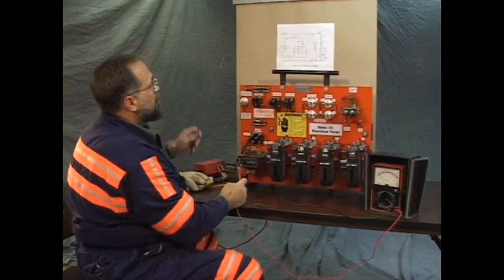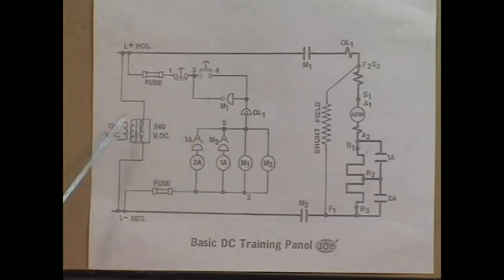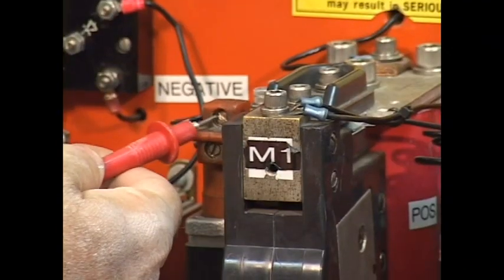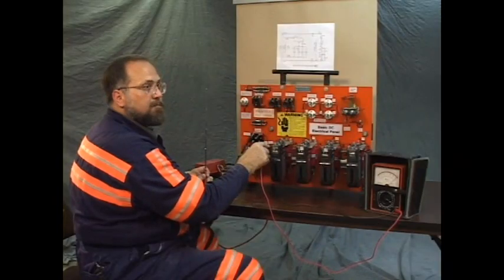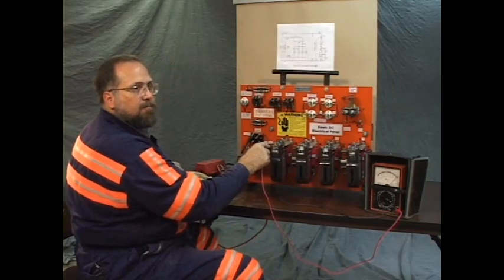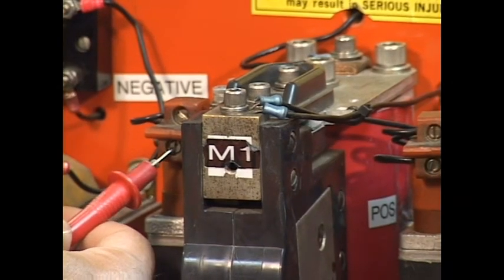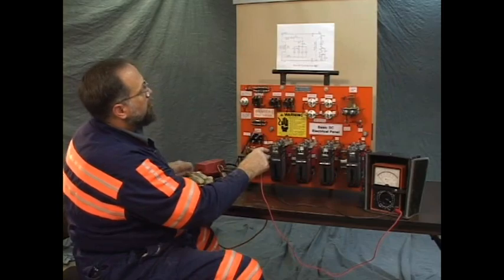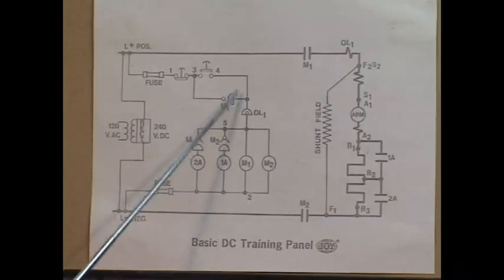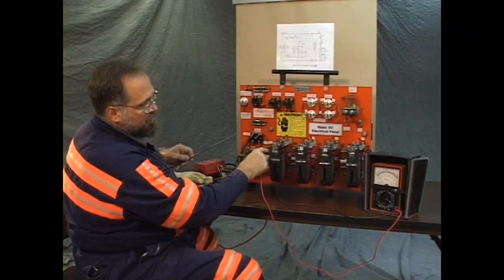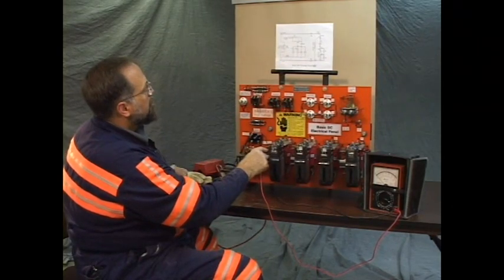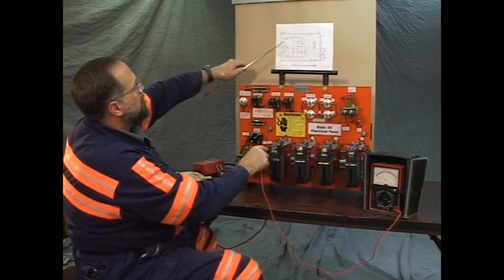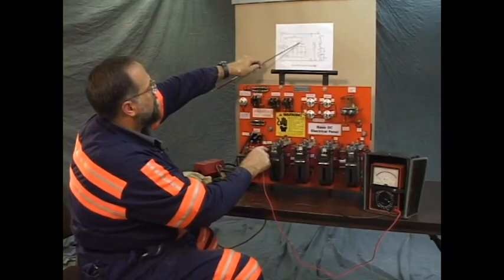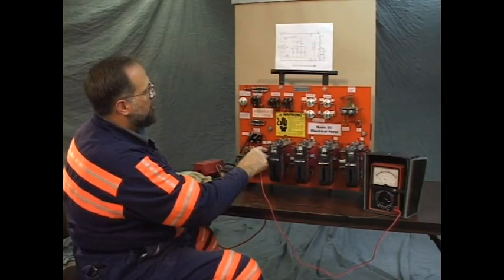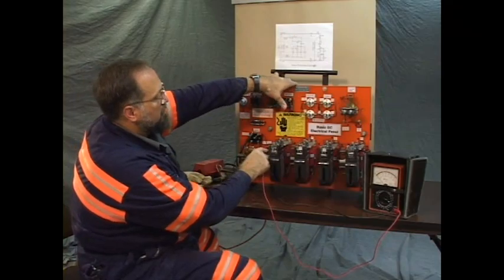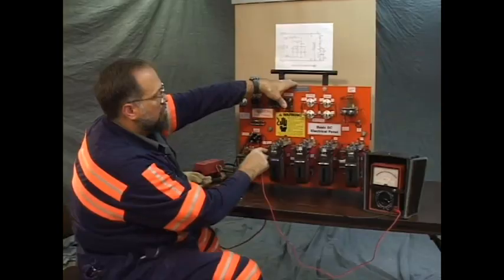All right. The next point on the print would be the top of the M1 mercury tube. And it's good. After that, we go to the bottom of the M1 mercury tube. The print illustrates this as being a normally open device, and as you can see by the meter, it is open. I'm going to test the start switch by depressing it while my meter lead is attached to the bottom of the M1 mercury tube, and I should have a circuit. The wiring is intact, and it is.